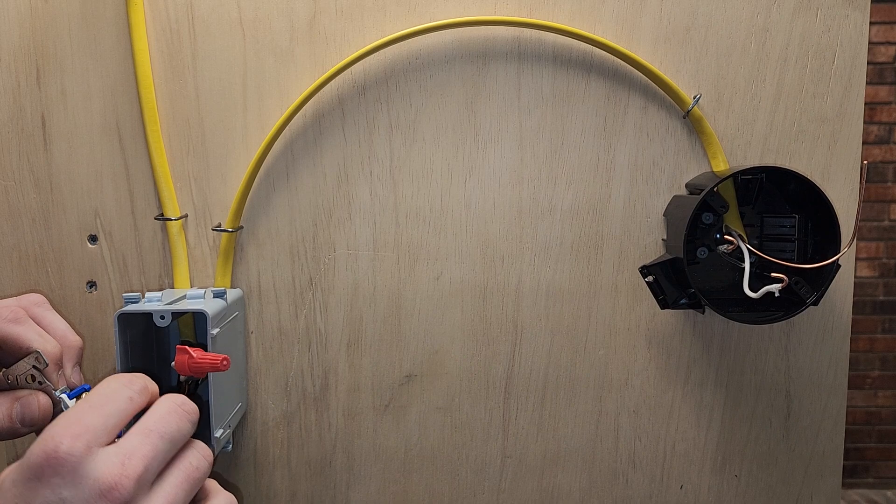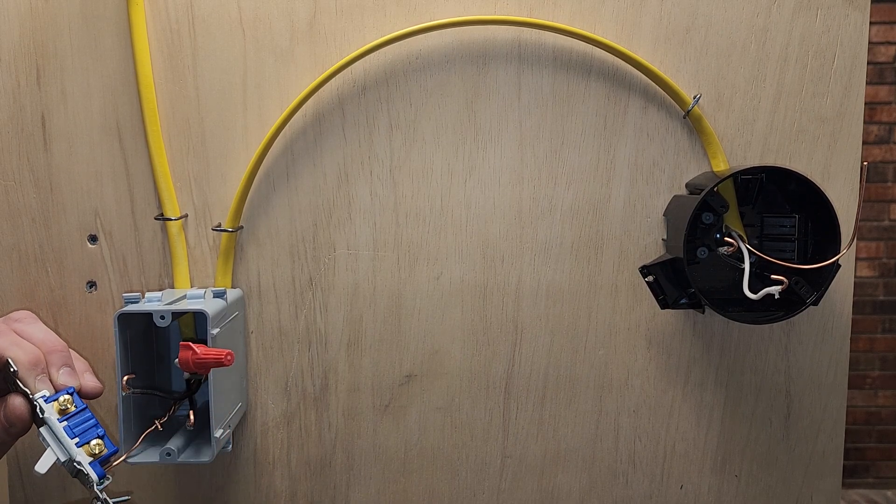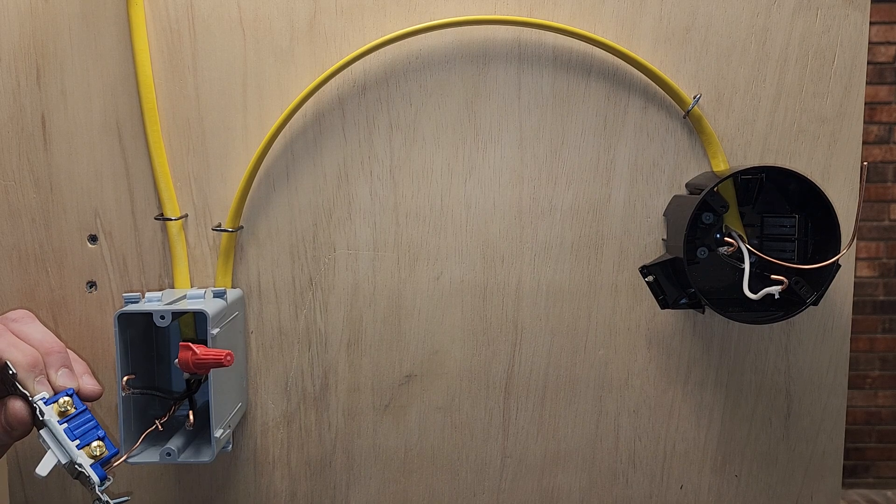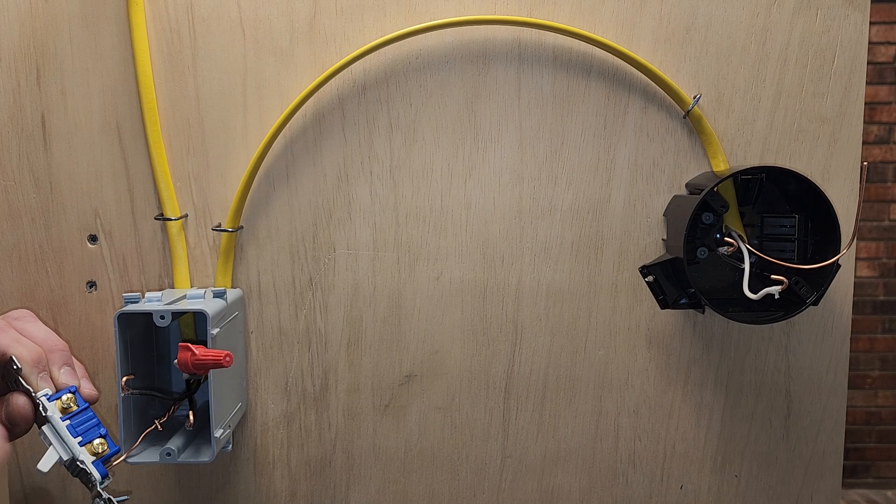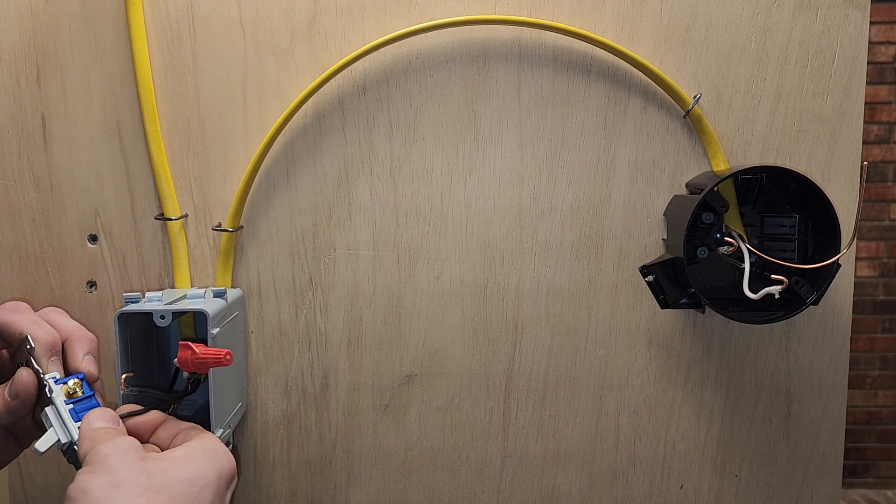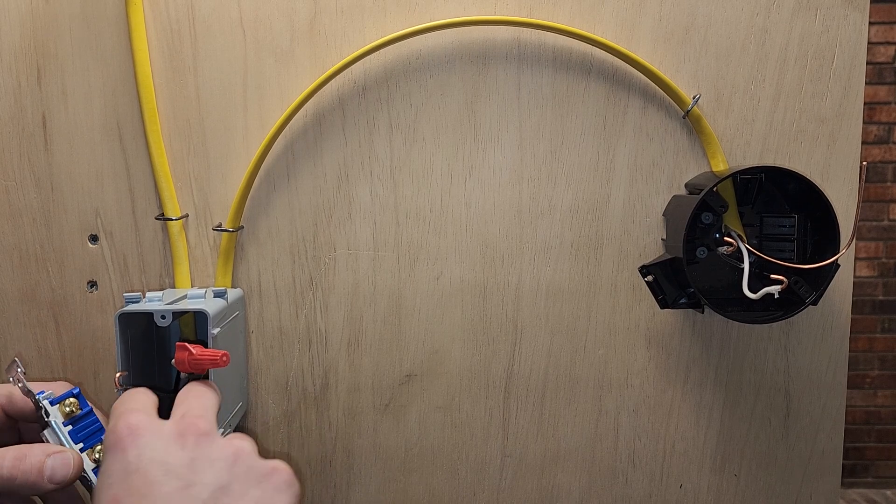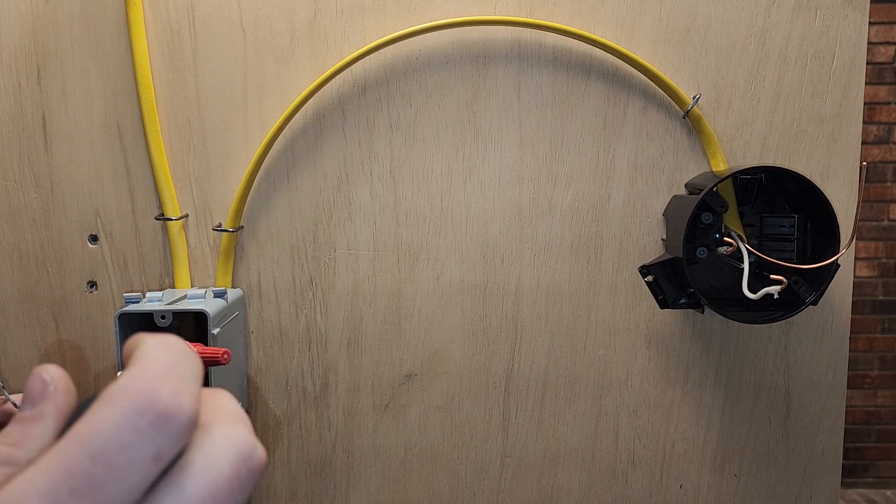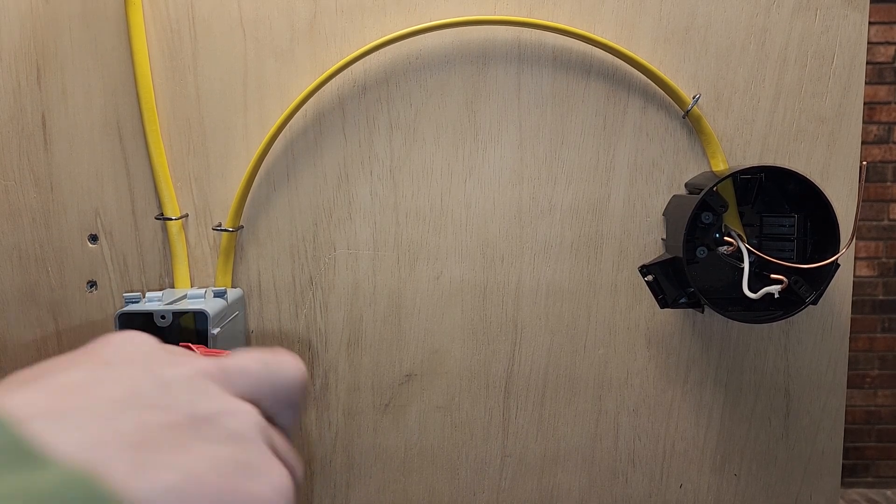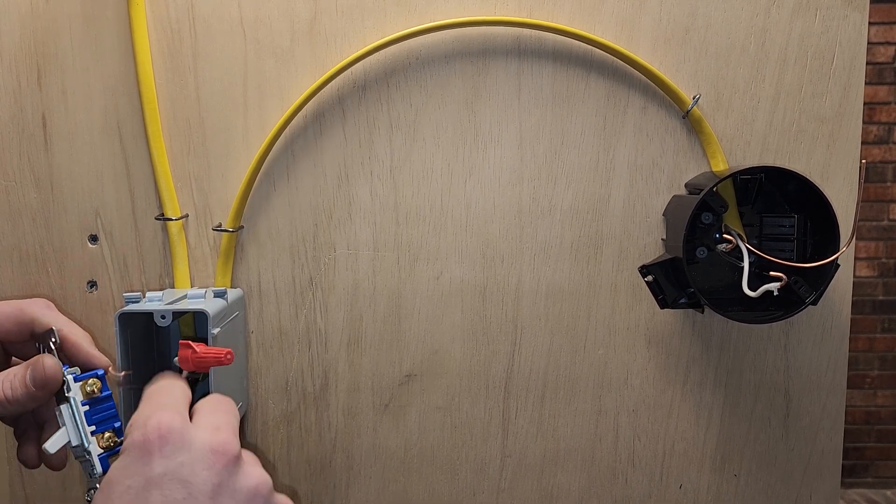Now, we have our two hots, our switch leg hot and our incoming power hot. It doesn't matter in theory where they go on the switch, but the best practice is always put power on the bottom. Anybody coming behind you, another electrician is going to assume power is on the bottom, but it doesn't matter. Power goes to bottom, our switch leg will go to the top.